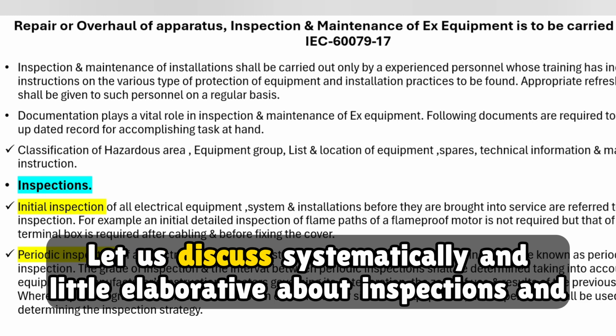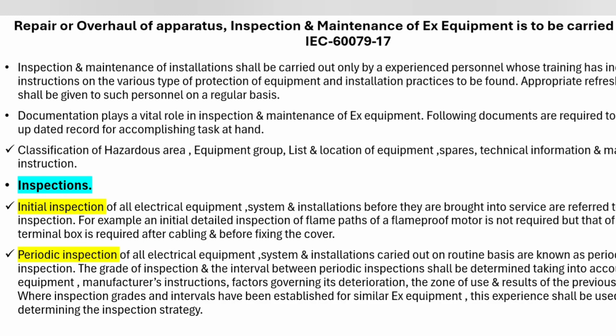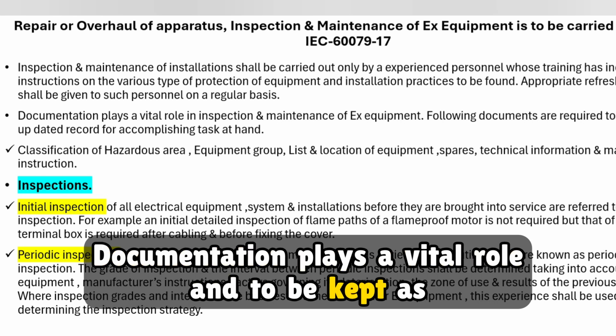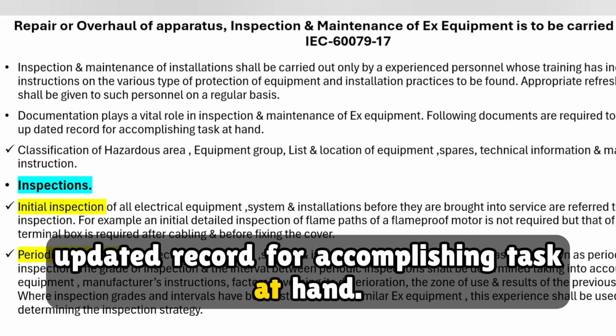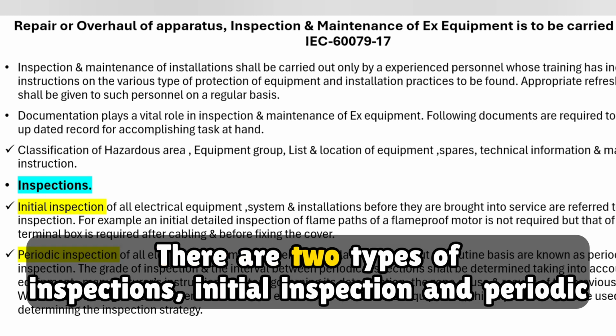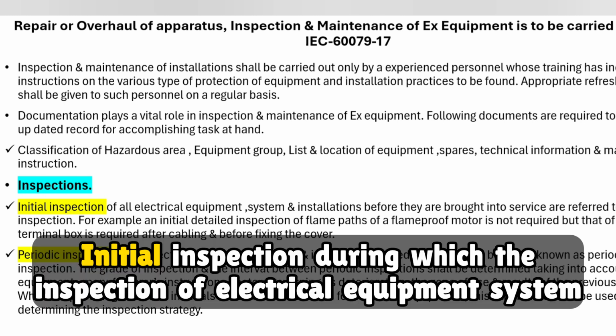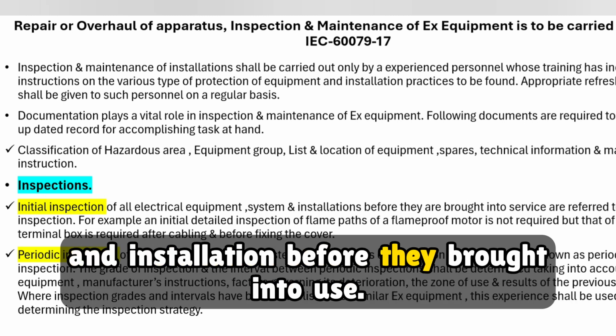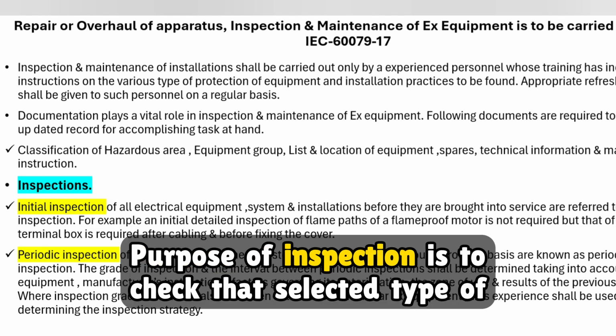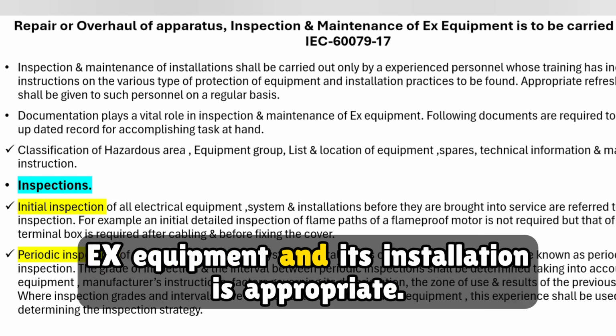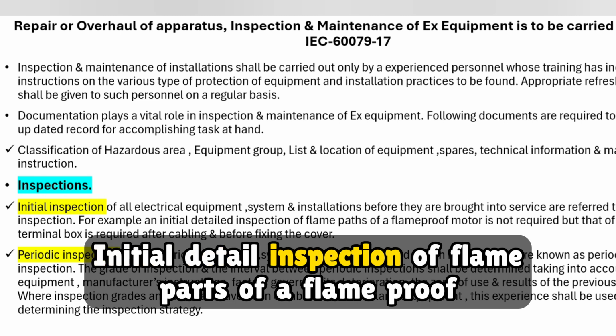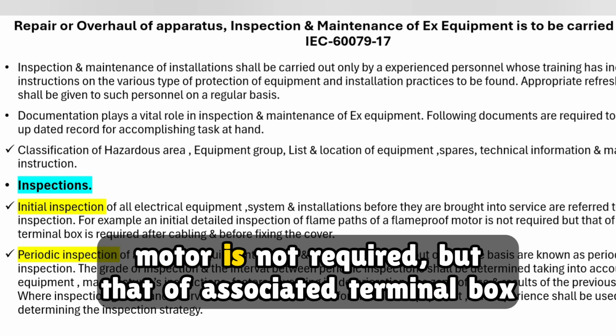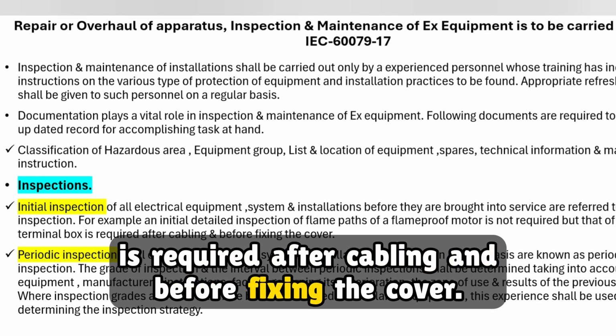Let us discuss systematically and a little more elaborately about inspections and maintenance of EX equipment. Documentation plays a vital role and is to be kept as an updated record for accomplishing the task at hand. Inspections: there are two types of inspections, initial inspection and periodic inspection. Initial inspection is the inspection of electrical equipment, system and installation before they are brought into use. The purpose of inspection is to check that the selected type of EX equipment and its installation is appropriate. Initial detailed inspection of flame paths of a flame-proof motor is not required, but that of the associated terminal box is required after cabling and before fixing the cover.